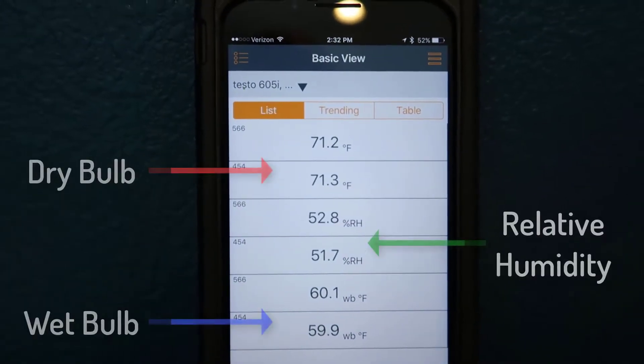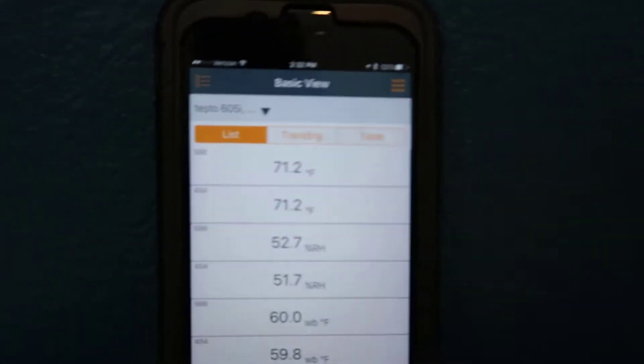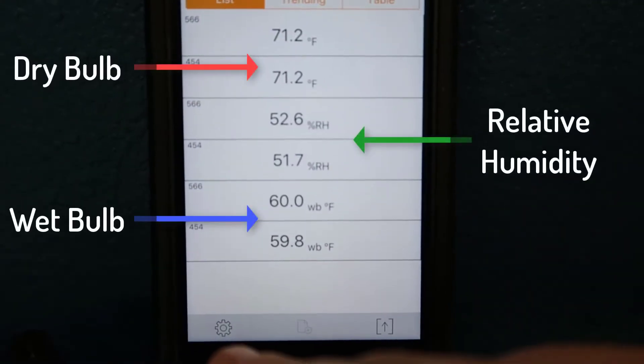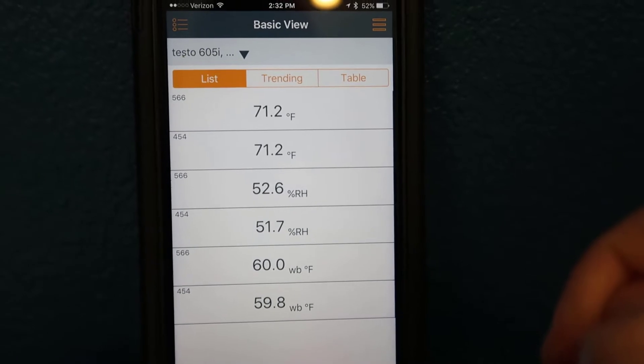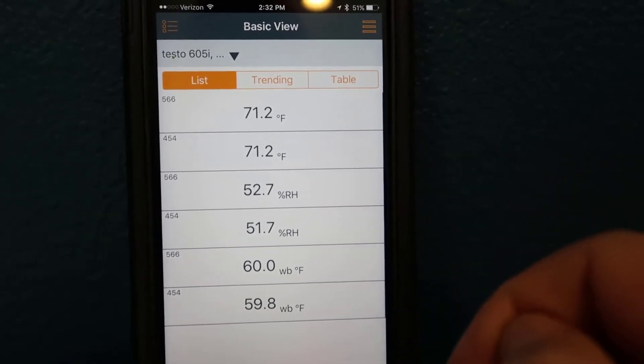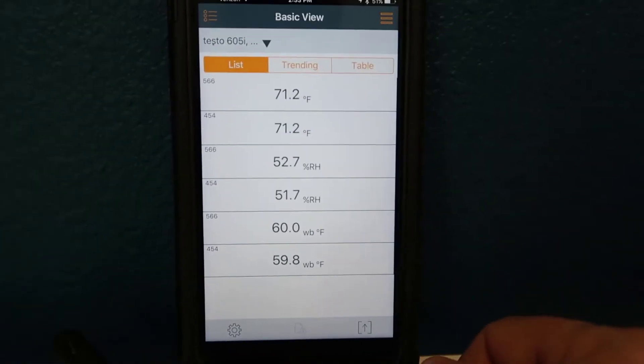As you can see, we're reading very close — we're actually dead on with the temperatures of the two. I have them set up side by side. You can edit the view; this is the basic view. You can slide them around, but I like to keep them side by side. Our relative humidities are actually 0.9 percentage points different from each other, which is within the tolerances. Our wet bulb temperatures are 0.2 apart. So they're well within the tolerances, and now we're ready to go ahead and make our reading.